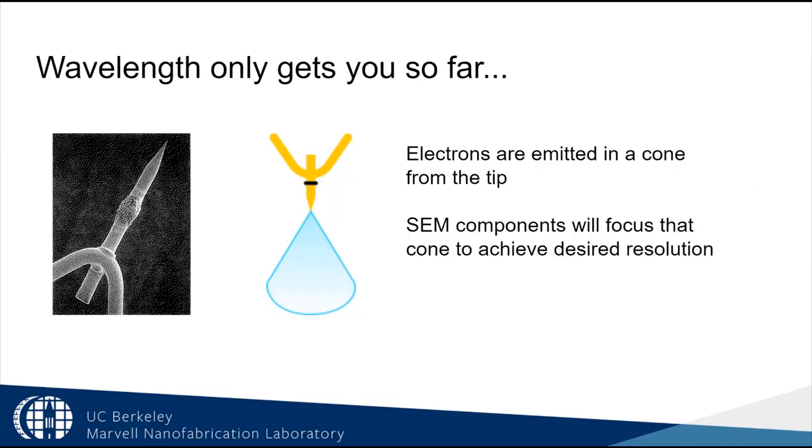All of the SEMs that we have in nanolab are field emission emitters. That means they have a thin tip attached to a filament. When we apply a potential voltage to that tip, we're able to extract electrons. Those electrons are emitted in a cone. We will be using the subsequent components to focus that cone down to get the resolution that we want.